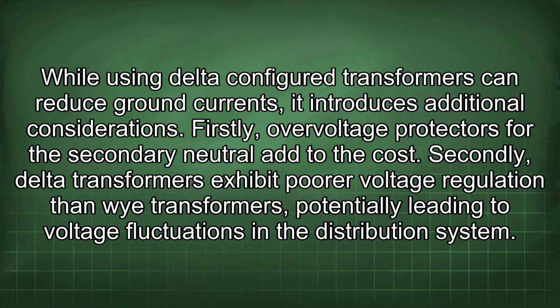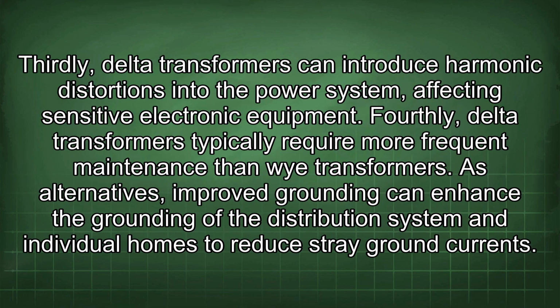Firstly, overvoltage protectors for the secondary neutral add to the cost. Secondly, delta transformers exhibit poorer voltage regulation than Y transformers, potentially leading to voltage fluctuations in the distribution system. Thirdly, delta transformers can introduce harmonic distortions into the power system, affecting sensitive electronic equipment. Fourthly, delta transformers typically require more frequent maintenance than Y transformers.